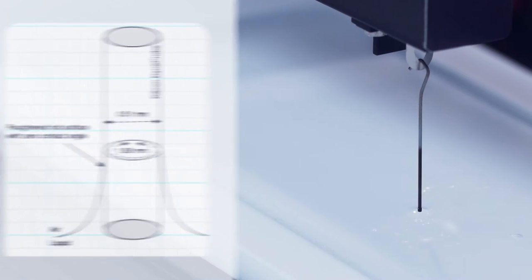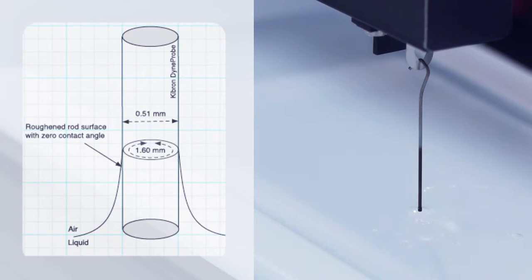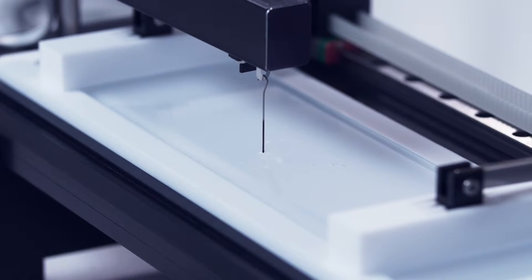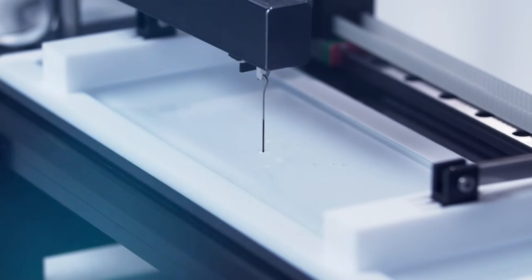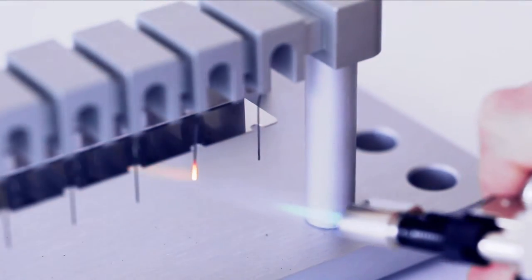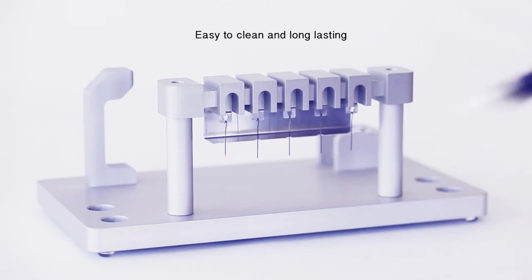The small diameter hydrophilic rod minimizes interference with the monolayer. During the measurement, the Dyneprobe is suspended across the air-water interface. Water forms a zero-contact angle with the hydrophilic oxide surface, which causes the liquid meniscus to rise up around the probe. The Langmuir Balance registers the corresponding force. Dyneprobes are easy to clean and long-lasting.